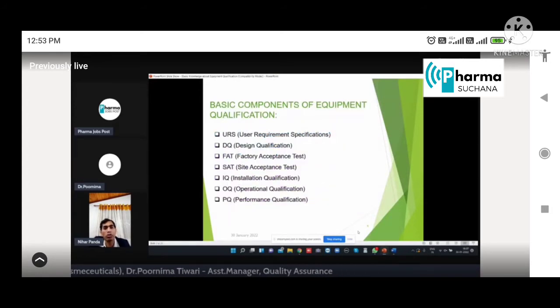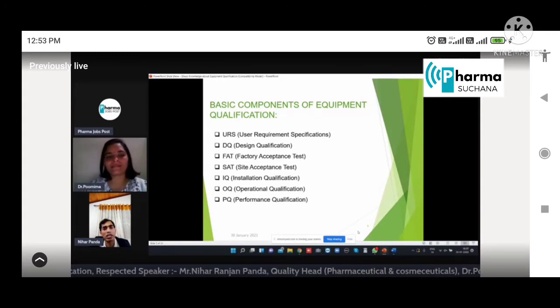What are the basic documents as per the current market scenario and current industrial practice? What are the basic components of equipment qualification? Those are URS, user requirement specifications; DQ, design qualification; FAT, factory acceptance test; SAT, site acceptance test; IQ, installation qualification; OQ, operational qualification; and PQ, performance qualification. These are the basic components of equipment qualification. But along with this, many other documents are also necessary to complete an equipment qualification.